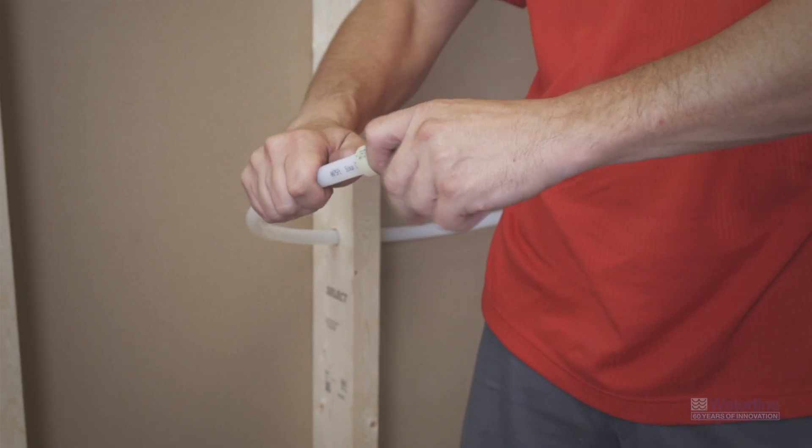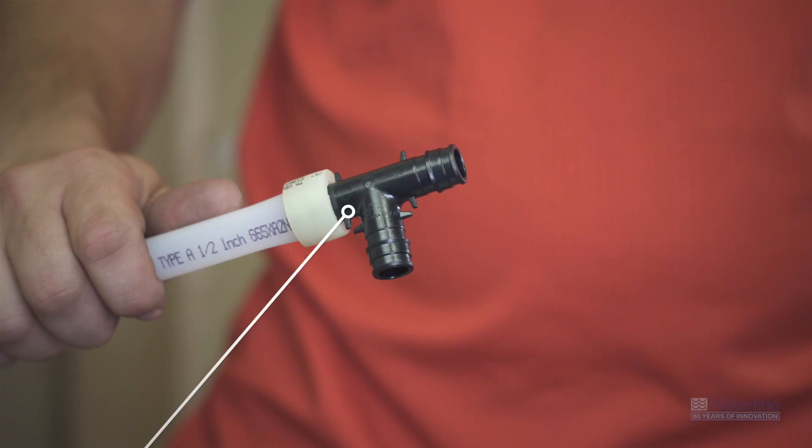Once you've expanded the pipe enough for it to reach the end of the expander head, you're ready to insert your fitting. When inserting your fitting, make sure you insert it until you reach the shoulder of the fitting. The tubing and the ring will begin to shrink back to its original diameter within seconds around the fitting, creating a secure connection. After a few seconds you're ready to make your next connection.